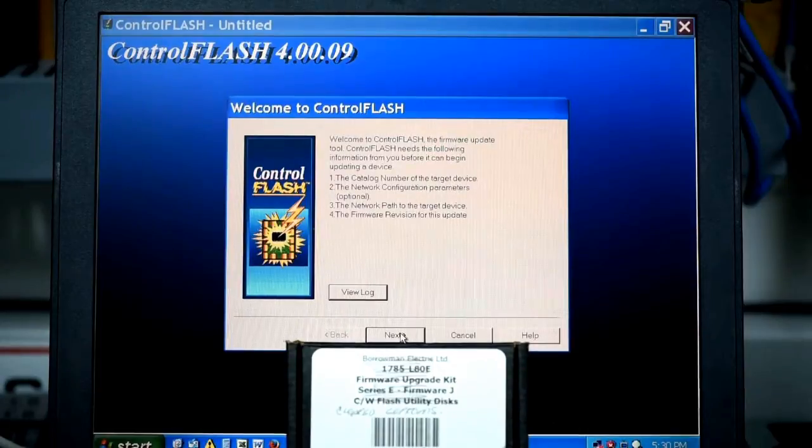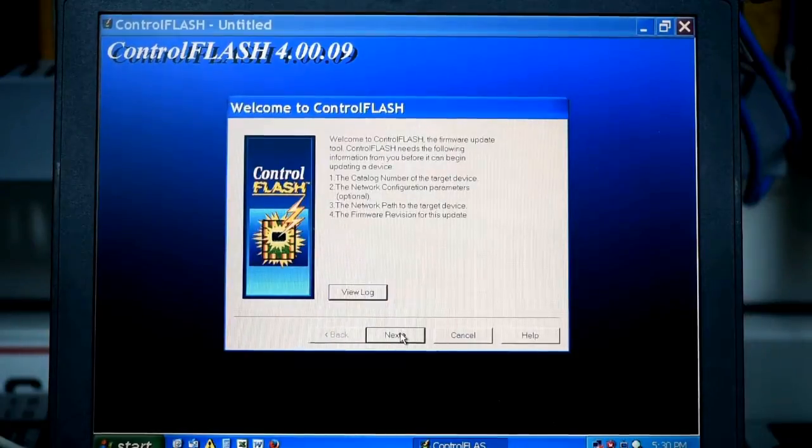you will get a firmware upgrade kit. I'm not sure, hopefully that's in focus. Yeah. This firmware kit that you used to be able to get from Allen Bradley or Rockwell contains 3.5-inch discs, and it contains 1-3 EPROMs in it, and that you have to use them all. We'll get into the EPROM part later. So anyhow, we open it up, and because the requirements are only RS-232, no battery, no other connections, and on the computer you're running, you must have RSLinx turned off and only this program running.